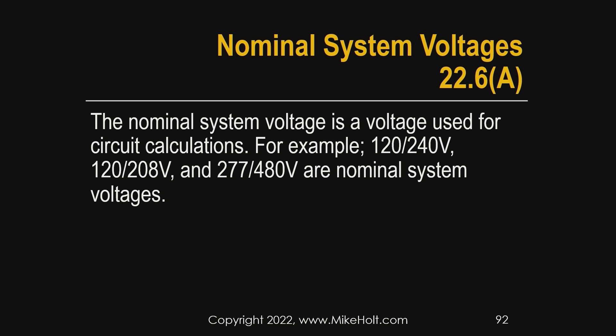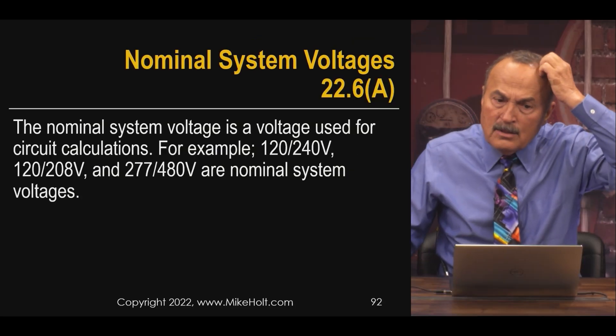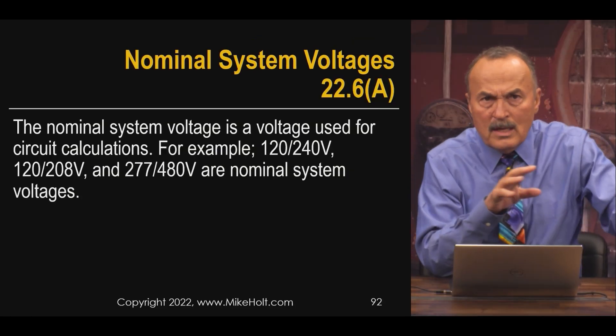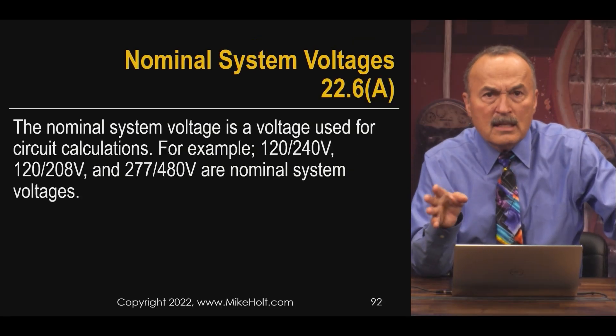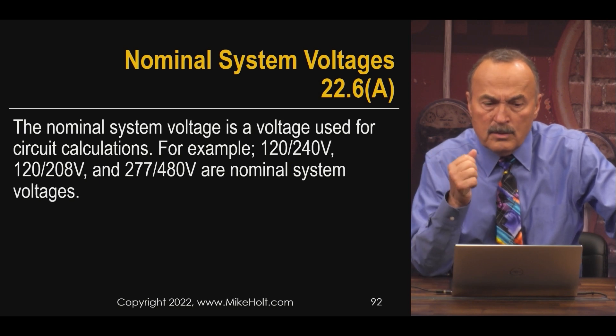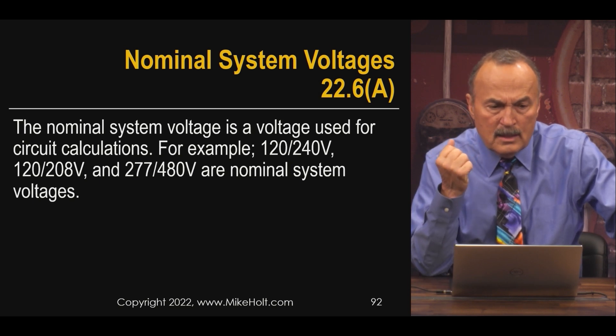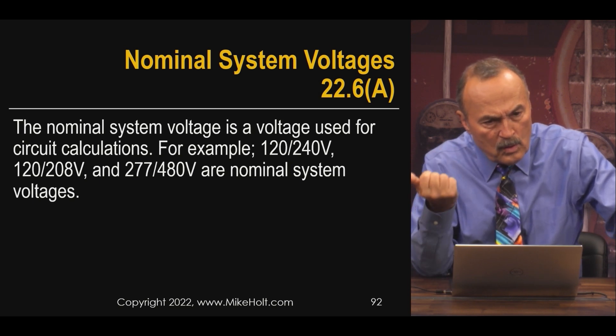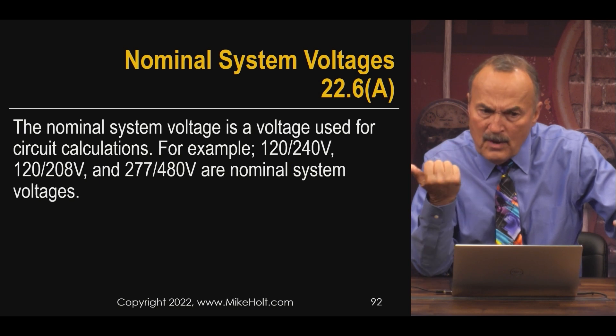In the National Electrical Code, when you're doing electrical calculations — it's NEC section 220.5A, voltages. Unless other voltages are specified, for the purpose of calculating branch circuits and feeder loads, nominal system voltages are used — 120, 120/240, 208Y/120, 240, 277/480.